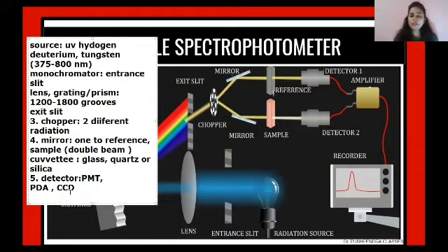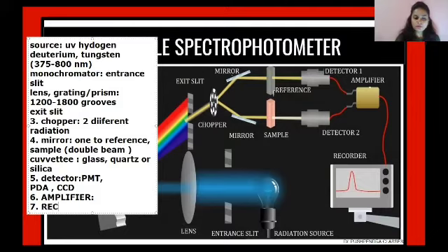Now then, after the detector has detected the signals, the proper photon and electron conversion signals will move on to the sixth part of the instrumentation, which is called the amplifier. Now, what is the main purpose of the amplifier? Whatever the detector has obtained, it will amplify to multiple levels because the signal might be of a very minute level.